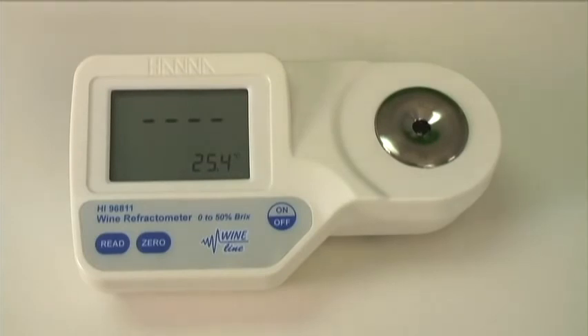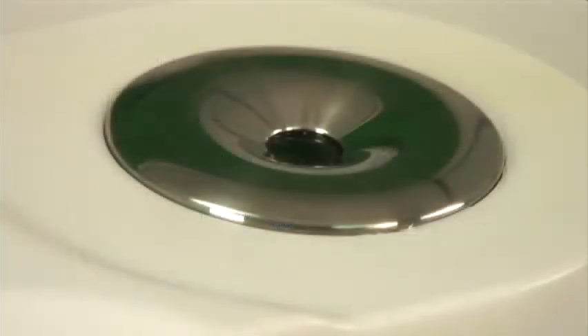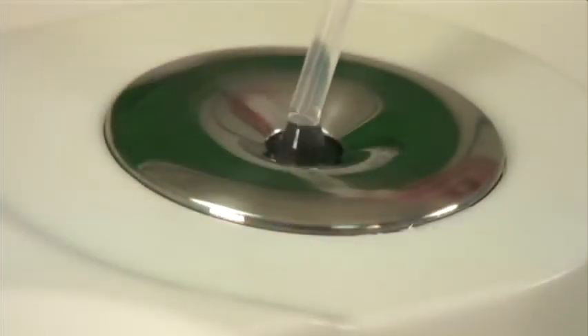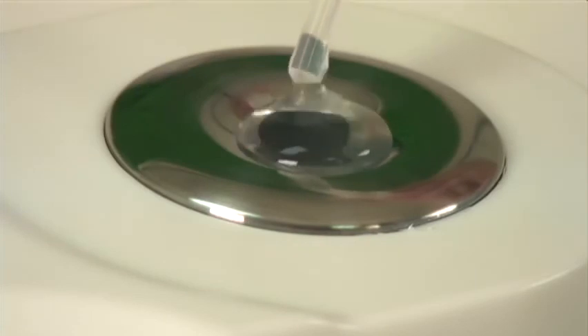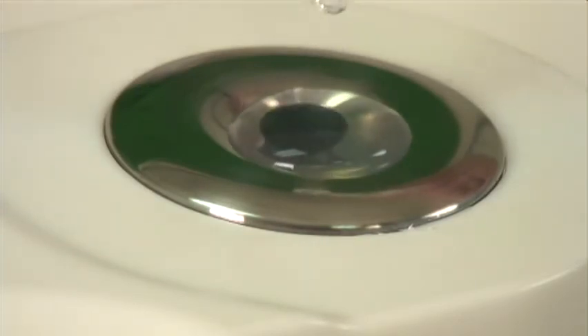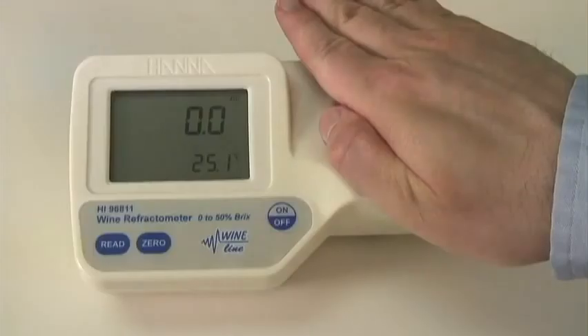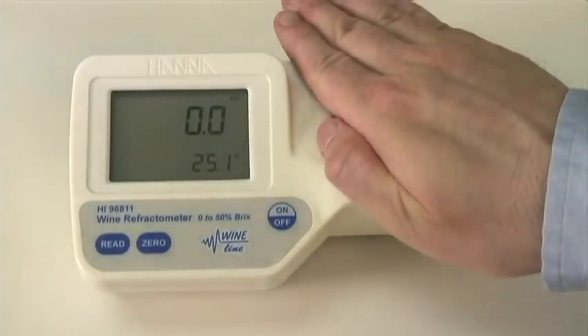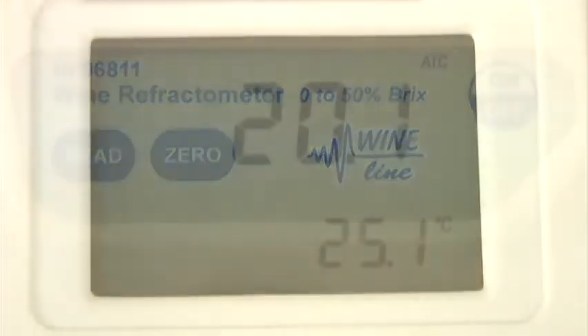Let's take a sample. This is pretty easy, just like calibration. First, make sure the prism surface at the bottom of the sample well is clear and dry. Using a pipette, fill the well with your sample. If there's a large temperature difference between the sample and the instrument, wait about a minute to establish an equilibrium. Cover it if you wish, and press the read button. The results are displayed on the screen. And that's how you measure sugar using the HI96811 digital refractometer.